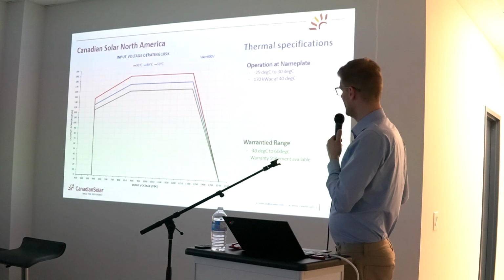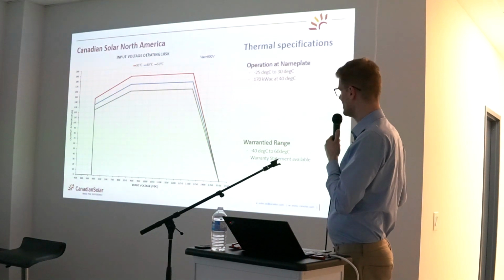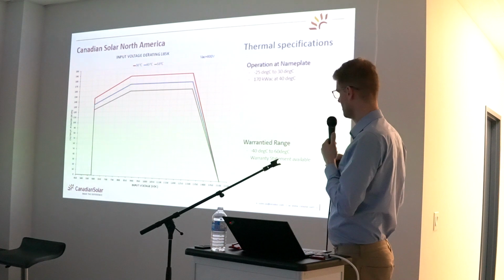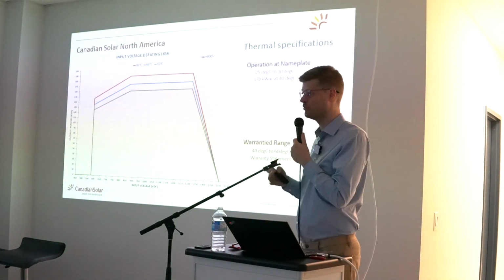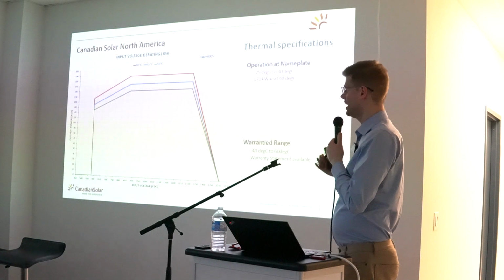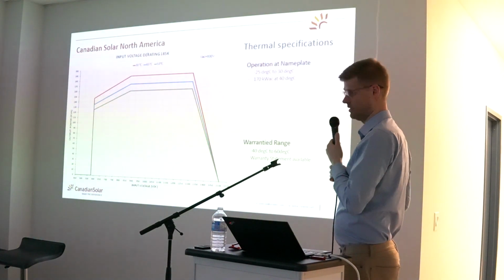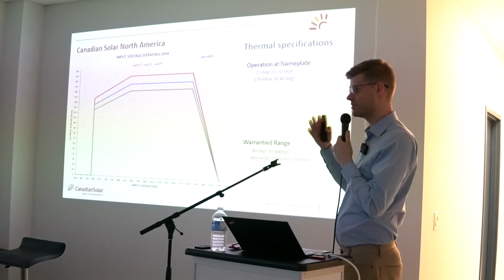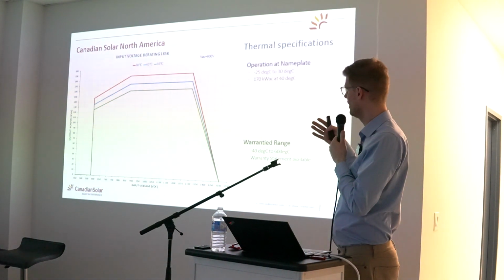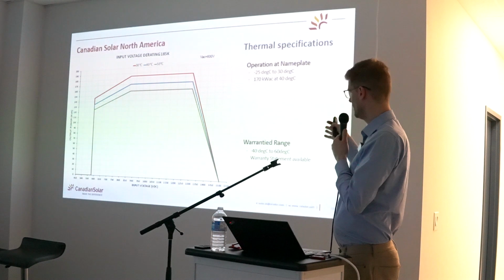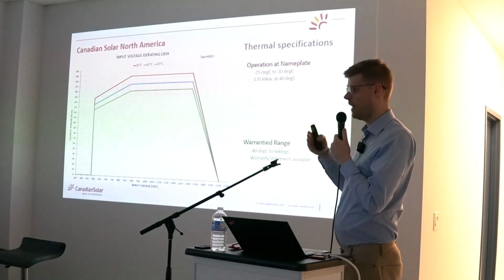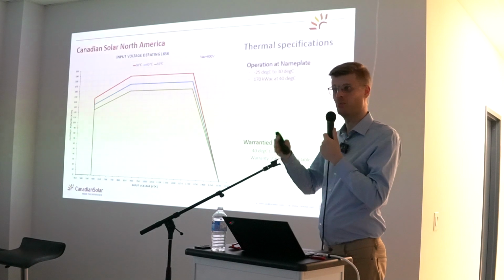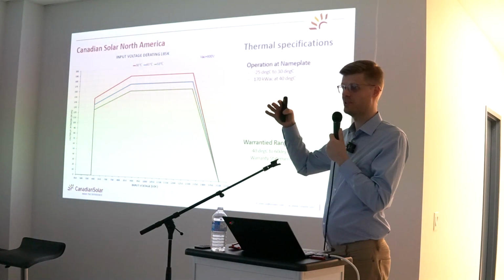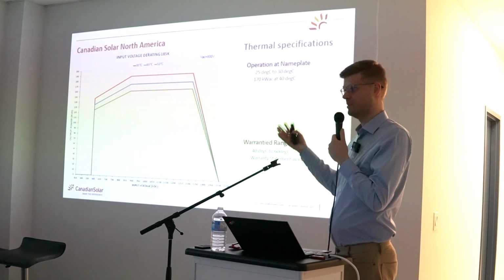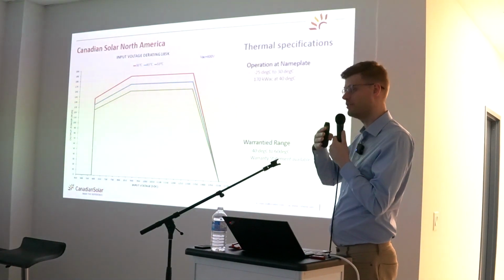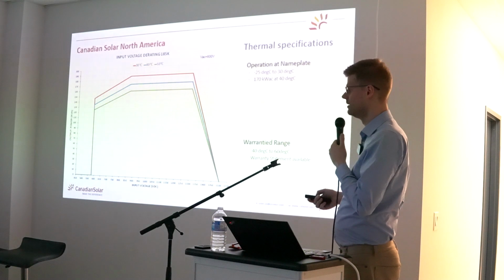For Canada, very specific, the warranted temperature range where the system can be installed goes all the way down to minus 40. That doesn't mean the inverter is operating at minus 40 degrees. So the operation range starts at minus 25 and goes all the way to 60, I think. Exactly. And the inverter will just wait until the internal temperature is -25, and once it is -25, then it will start the operation, and with the inverter operating, you have some power losses, the system gets even warmer, and you ramp up the power relatively quickly.